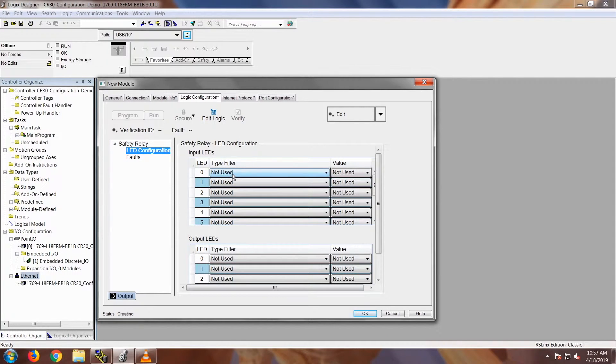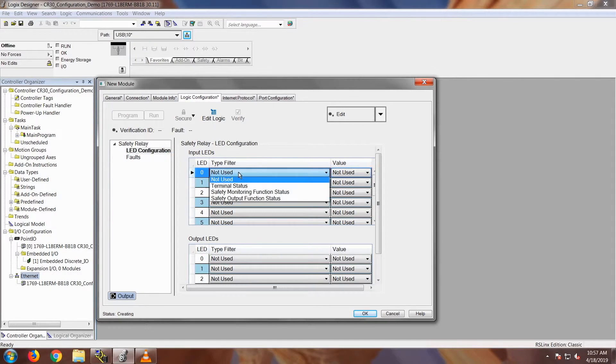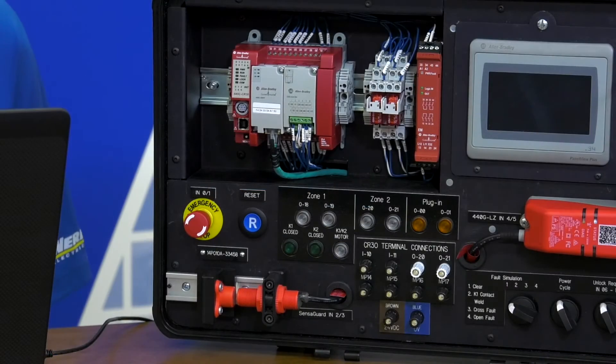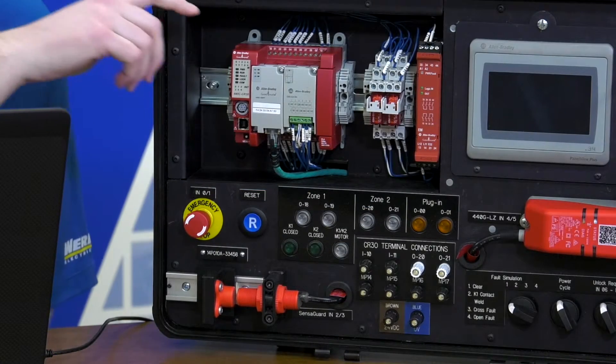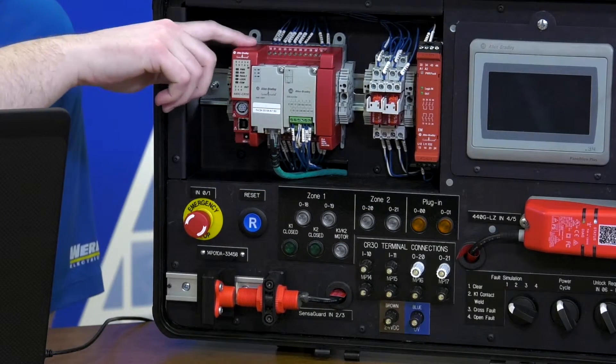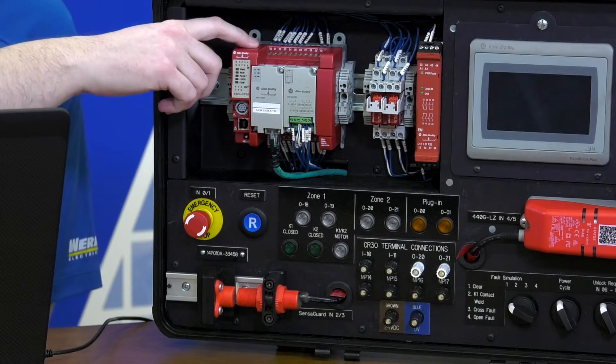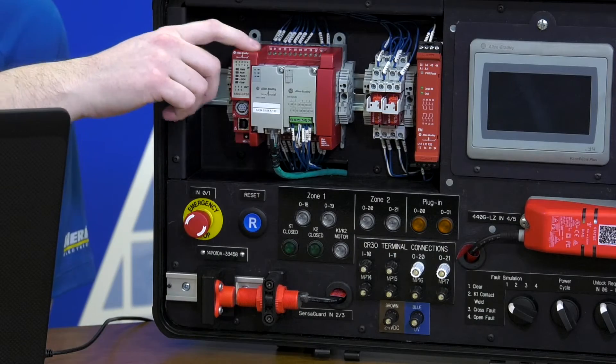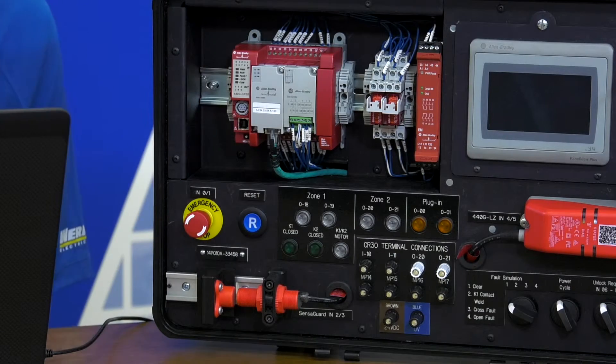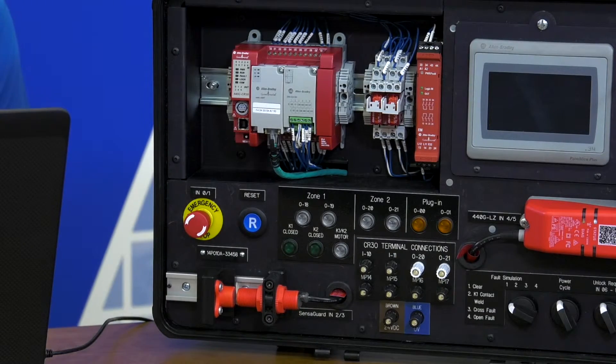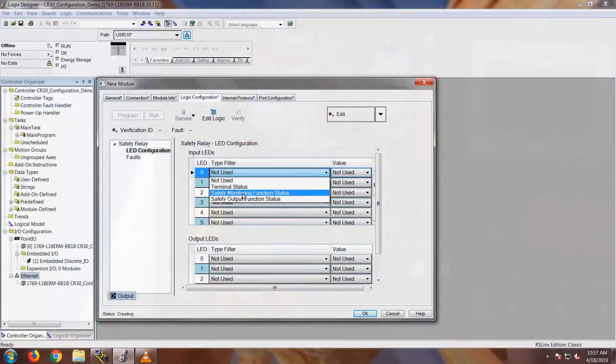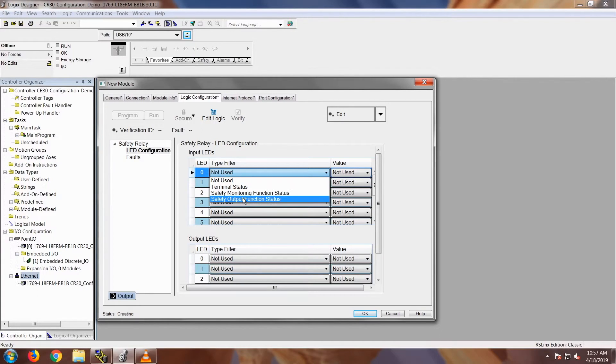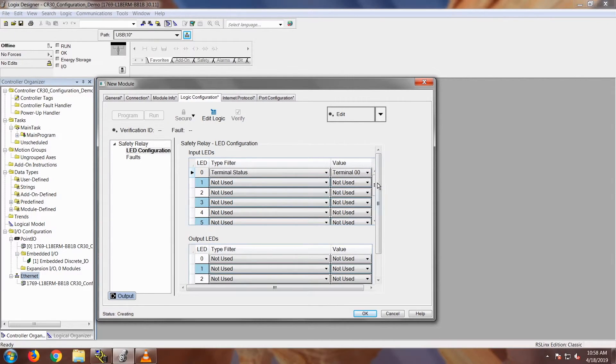So if you notice right here, they are defaulted at not used. So you can open this up and then you can get just terminal status, which would be basic terminal status of the actual point or the input points on the unit or the output points on the unit. And then you can also monitor safety monitoring functions, which is part of your logic when you program the device. Or you can monitor the safety output function status. So I'm going to go ahead and click on terminal status quickly just to show you.